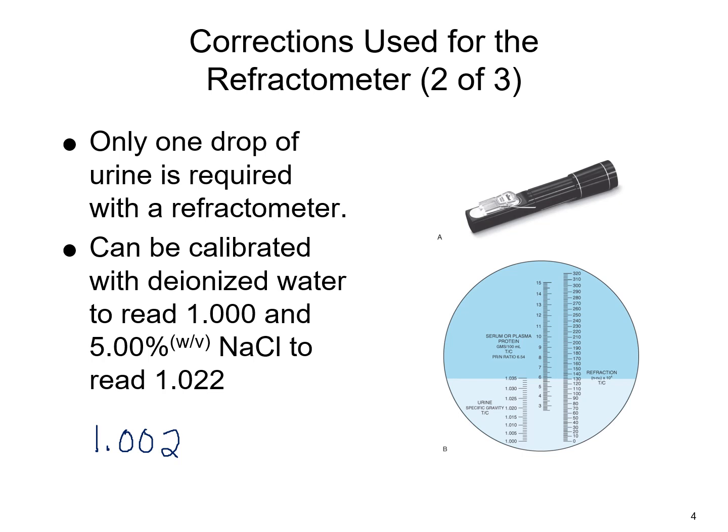Well, because it's reading 0.002 over that calibration value, for any sample that you read after that, you're going to have to account for that difference. So you would need to subtract that 0.002 from every sample value that you got from then on. And that's part of your quality control process for that particular sample based off that calibration.